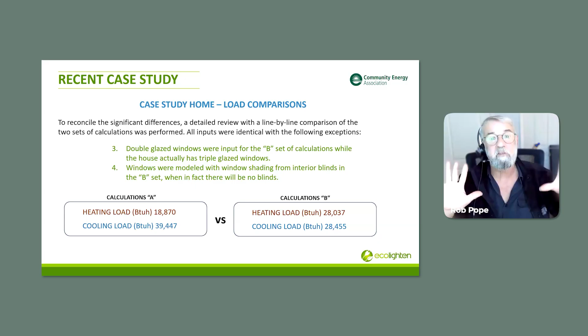Even if there's going to be blinds and they promise, 'oh I swear I'm going to close those blinds, I'm never going to open them' — which you'd be a fool to believe — even if they did do that, it would have extremely minimal, inconsequential impact on the cooling load. But it's in here, and it's a substantial amount of shading, 50% is what they put in for this. Obviously that's going to make a massive difference.